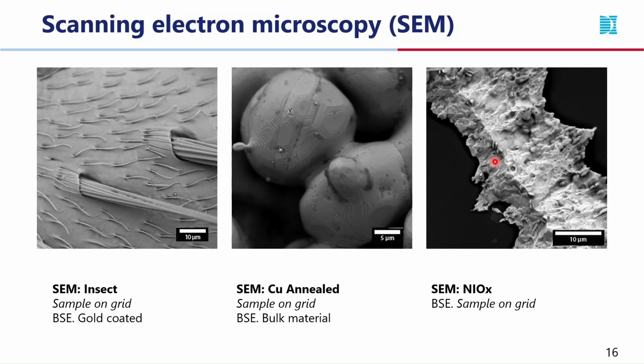Although LVEM25E is not a dedicated SEM device, it's still a very powerful tool with a resolution of approximately 3 nanometers. There is only one disadvantage. The device uses an immersion system of TEM optics, so the sample is loaded between the pole pieces, and there is not unlimited space between them. Thus, the sample has to be comparable in size with a TEM grid.